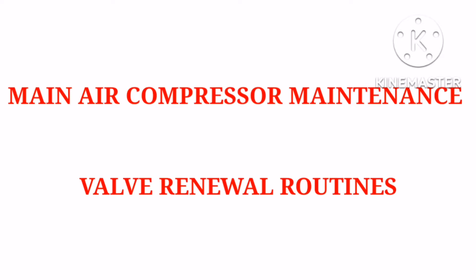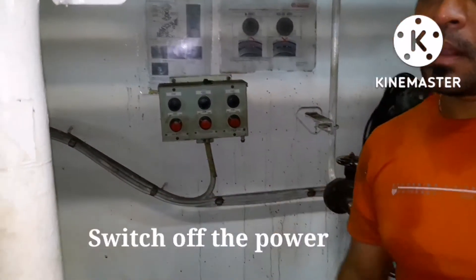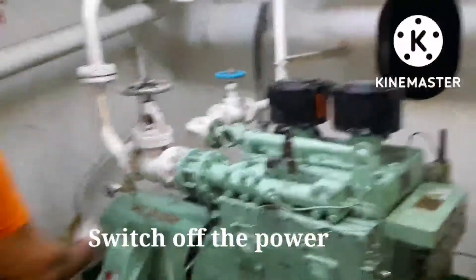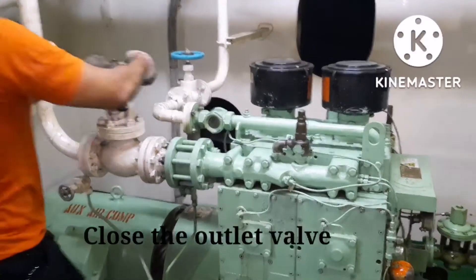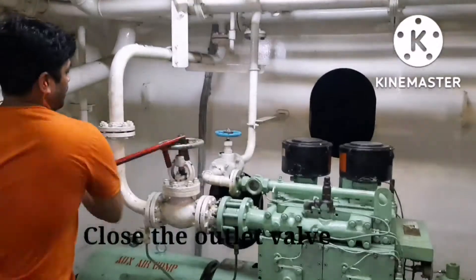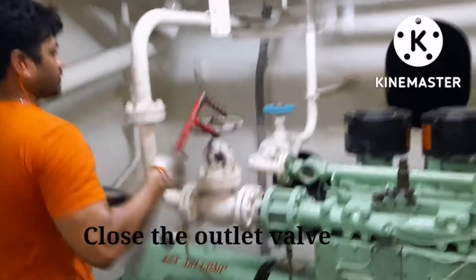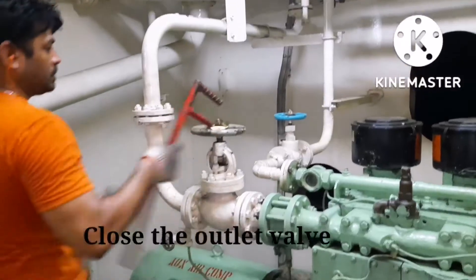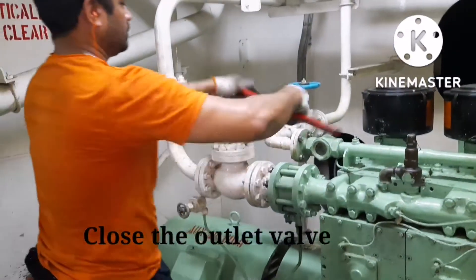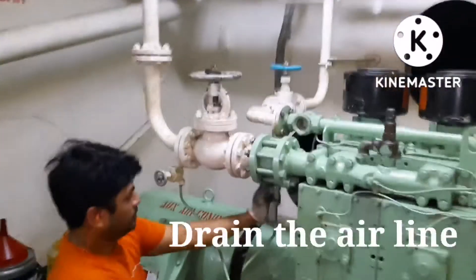We will show something about main air compressor maintenance. Whenever you do maintenance on a main air compressor, you have to switch off the power and then close the outlet valve of the compressor you are maintaining. The reason is, if the valve is not holding, air from the other compressor can pass through and cause injury. That is why we close the outlet valve of the compressor first.